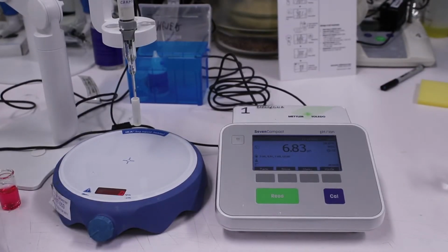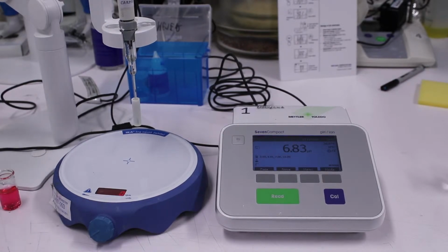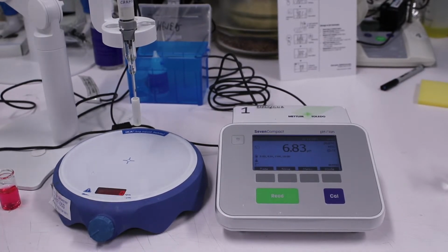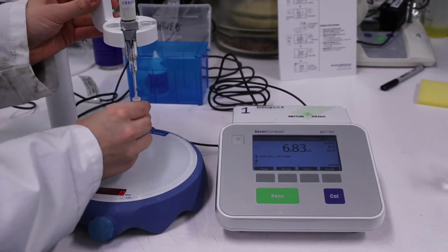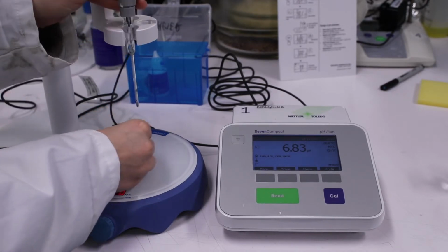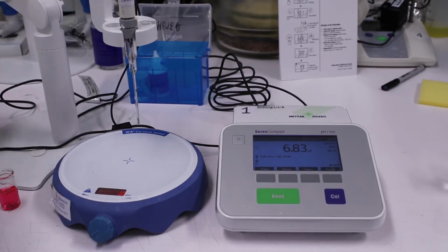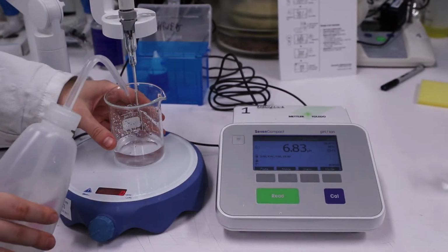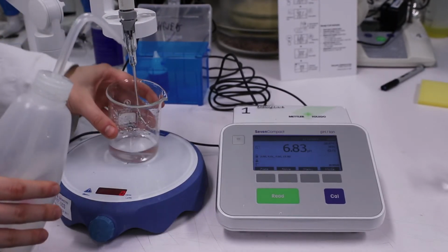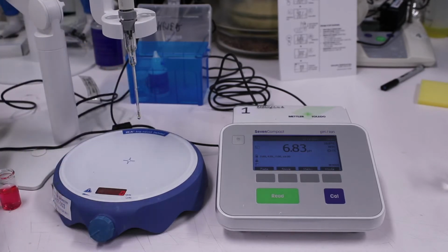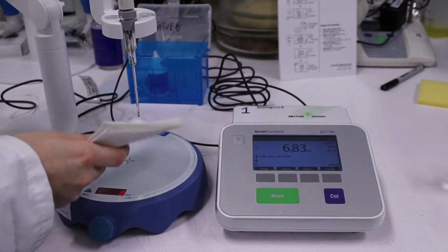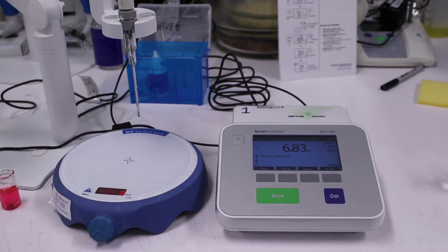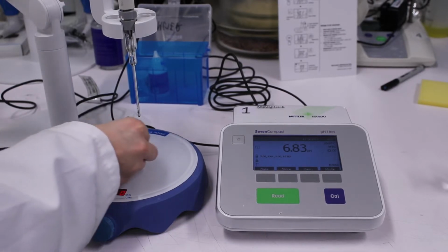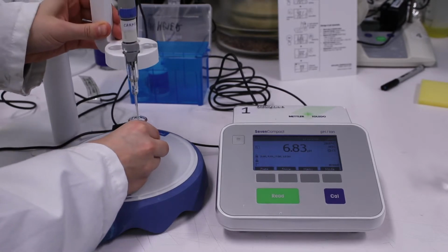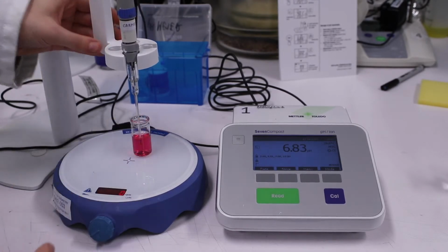Now that we've learned how to calibrate the pH meters, I'm going to teach you how to take a basic measurement. The first thing that we need to do is remove the cap and rinse it with deionized water. Dab the end of the electrode lightly to remove the excess water and place the tip into the solution. To take the measurement, press read.